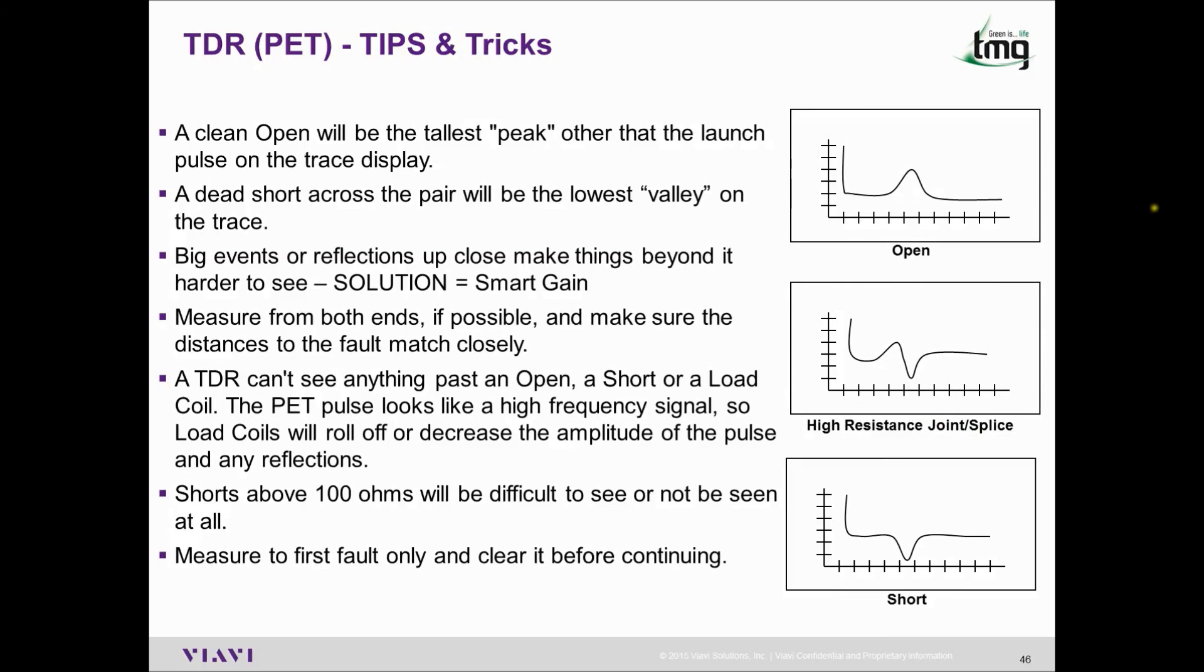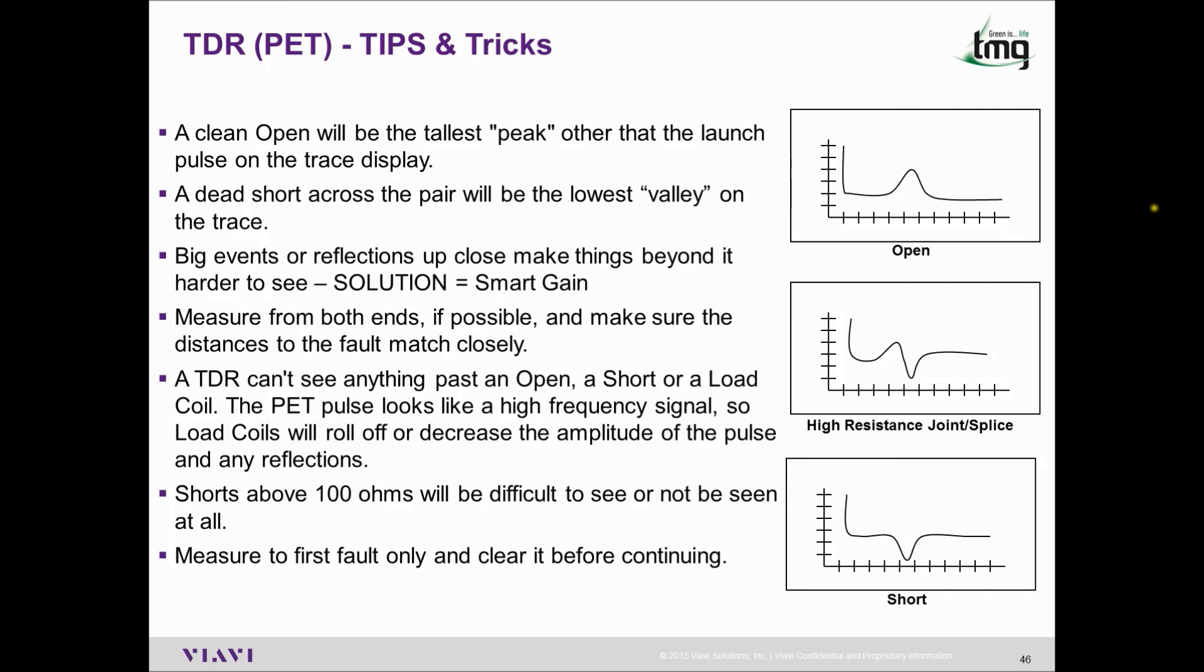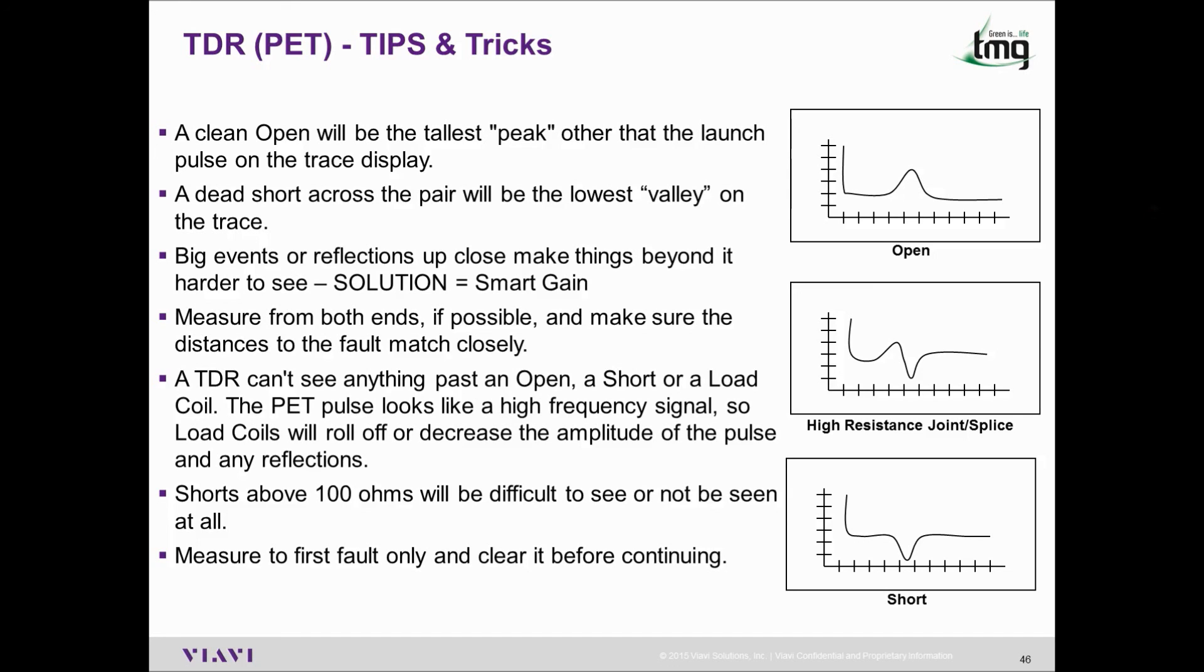Here are some tips and tricks with regards to the TDR. A clean open will be the tallest peak other than the launch pulse on the trace display. A dead short across the pair will be the lowest valley on the trace. Big events or reflections up close make things beyond it harder to see. The solution is to use smart gain. Measure from both ends if possible and make sure the distance to the fault match closely. A TDR can't see anything past an open, a short, or a load coil. The TDR pulse looks like a high frequency signal, so load coils will roll off or decrease the amplitude of the pulse and any reflections. Shorts above 100 ohms will be difficult to see or not be seen at all. Always measure to the first fault only and clear it before continuing.